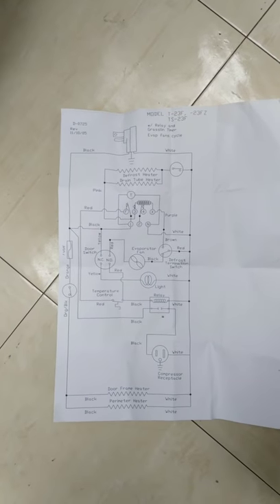So I got a call for this little guy. Get out, your fan motor's not coming on. He said he cleaned the coil. And then the fan motor took a crap. It's got a really nice diagram. It's a T23F. So, this looks like we got a bad condenser fan motor.